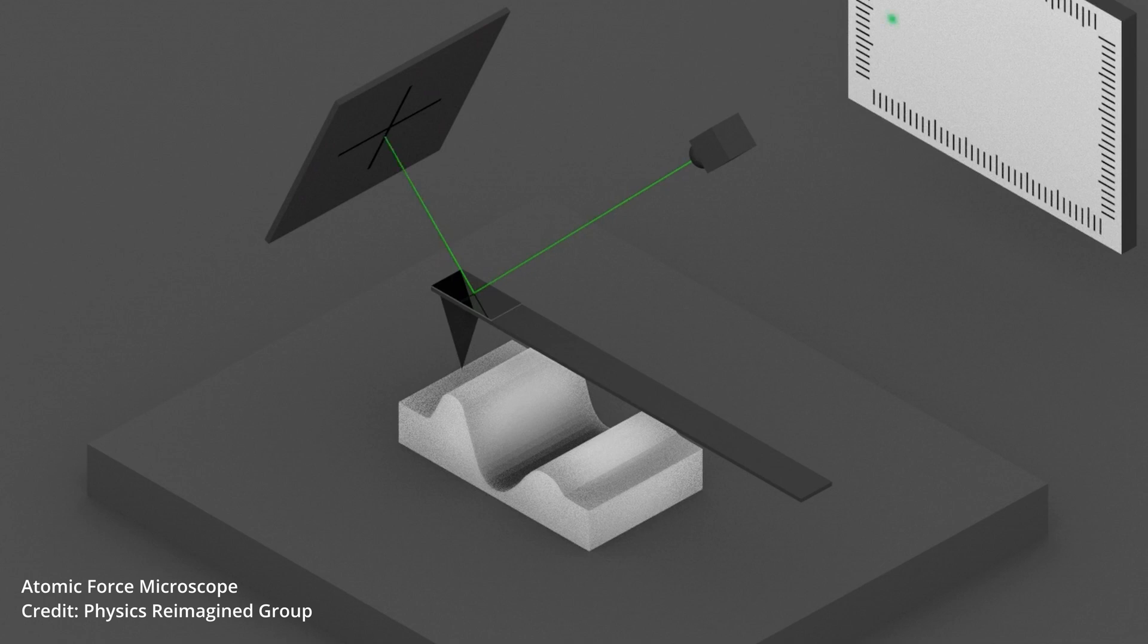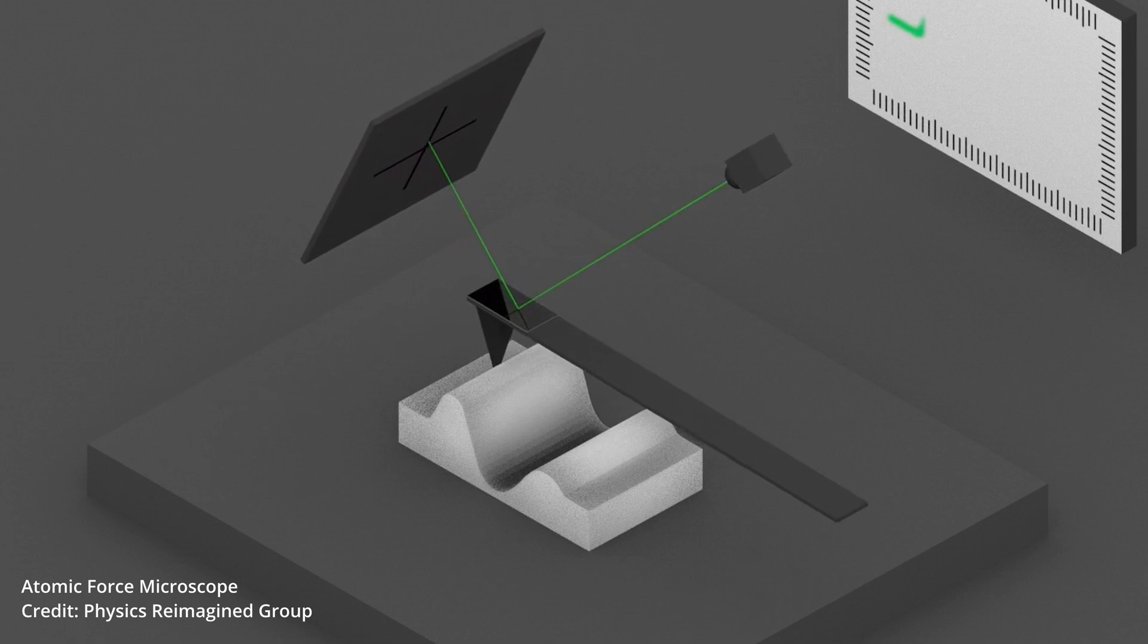The AFM tip scans the surface, moving up and down as it scans because of the surface topography. The up and down movements cause laser beam shifts to be picked up by the detector.